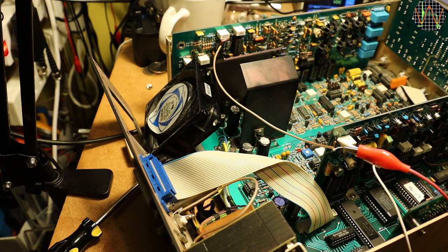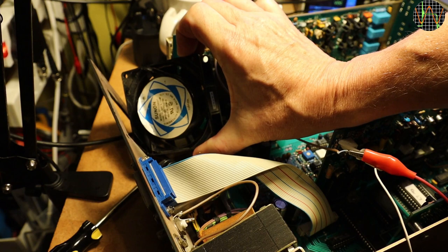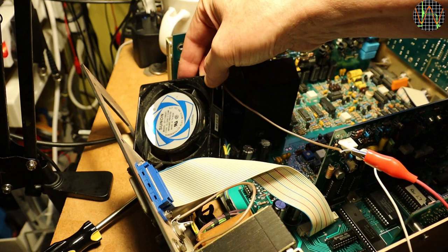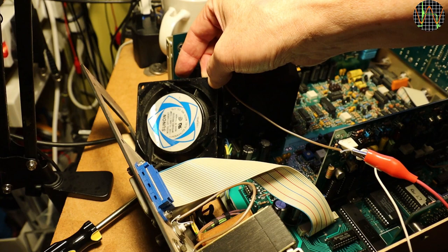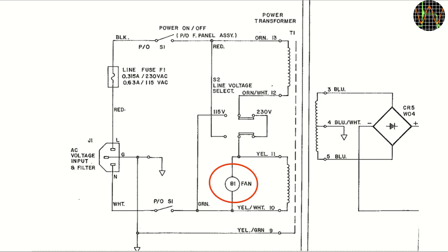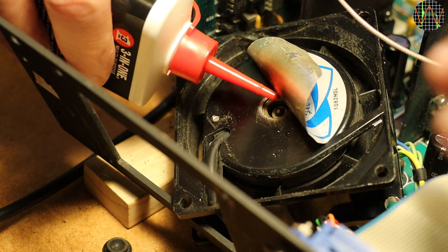The problem is that this Sunon fan is a 115V AC type and new 115V types of this size are very expensive to get in a 230V country like the UK. I am looking for a new one because replacing a used fan with a used fan makes little sense. The fan is quite ingeniously wired with a transformer and the mains voltage selector to work at 115V regardless what mains voltage is selected. It would be a shame to replace that with a hardwired 230V type so I decided to repair it for now and worry about replacement later once I know that the generator is actually fully working again.